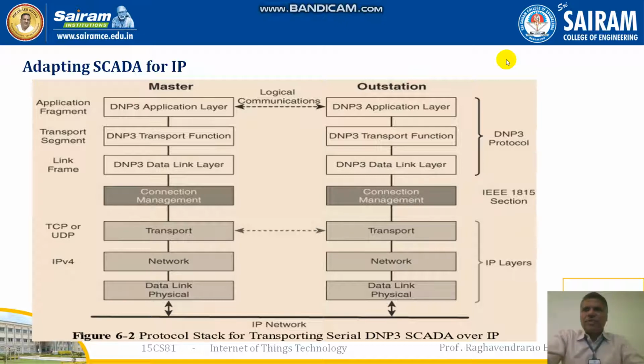Outstations monitor and collect data from the devices that indicate their state, such as whether a circuit breaker is on or off, and take measurements including voltage, current, temperature and so on. This data is then transmitted to the master when it is requested, or events, alarms and control commands can be sent in an asynchronous manner.